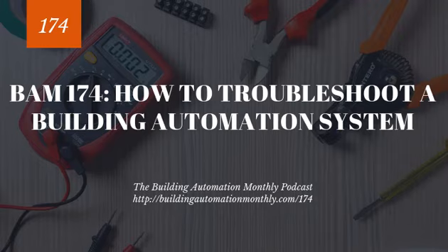If it is something simple like a VAV box airflow, I know I just told you, hey, check the inputs first, but you can get away with saying, you know what, I'm just going to make sure the damper's actually open and stroking, and I'm going to make sure the CFM set point is right, and work my way backwards. You can do that as well. But with either one of these, the thing you don't want to do is bounce between the two. You don't want to start with zone temp, and then check the damper, and then go back to the zone temp PID, because you're wasting time, you're being inefficient, and you aren't providing a troubleshooting path. Now, VAV box is a very simple example, okay?